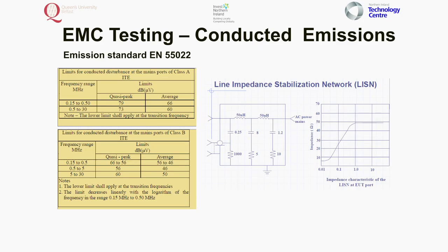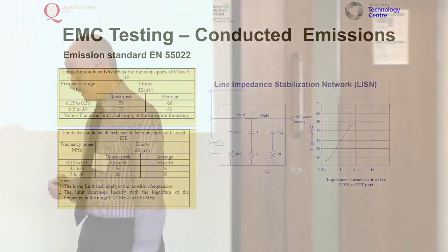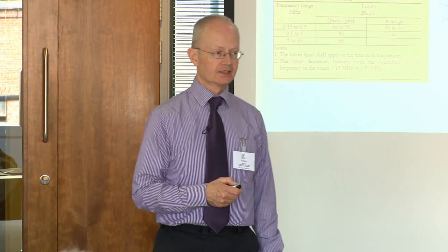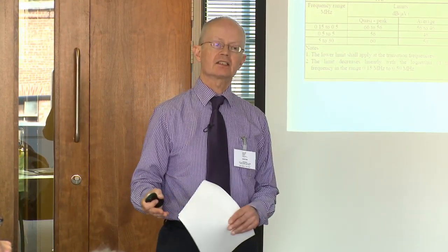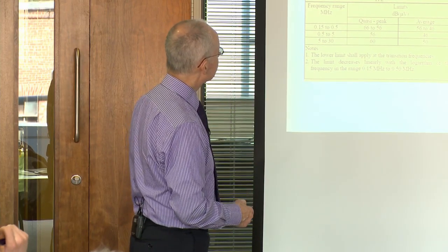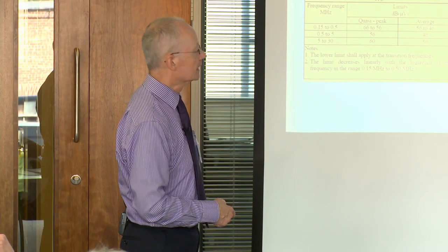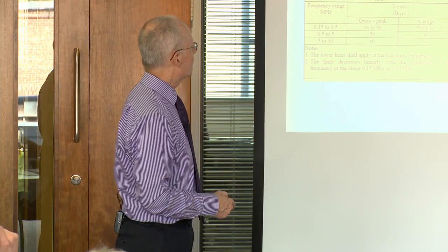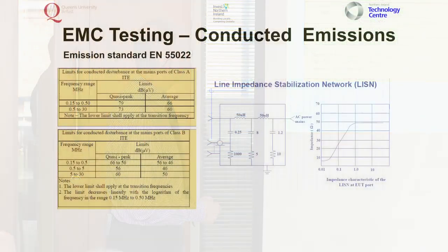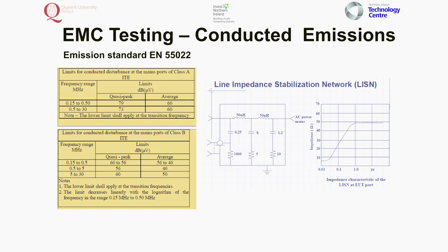For conducted emissions, you use a receiver but this time there's a Line Impedance Stabilisation Network — a LISN. It doesn't have to be done in a shielded room, although I do it in a shielded room, but it's a different shielded room to the anechoic chamber. This stabilises the mains power coming in. There's no separate indication of neutral because it's done per phase — neutral is a phase as far as the LISN is concerned. The measurement is made live to earth and then neutral to earth — two separate measurements.